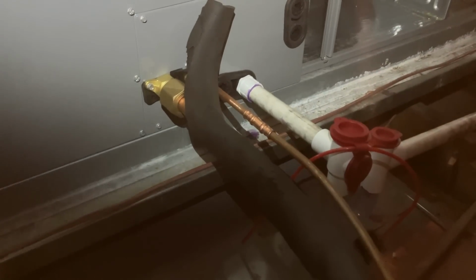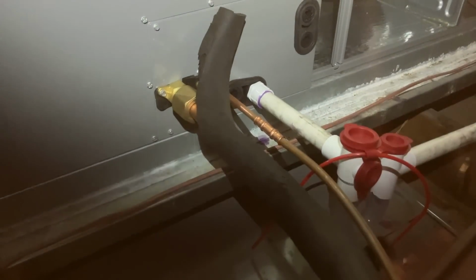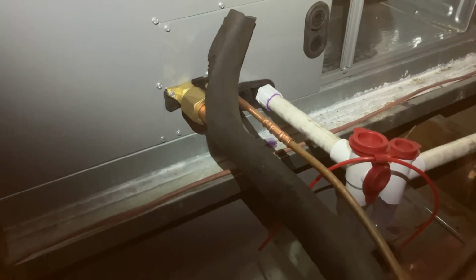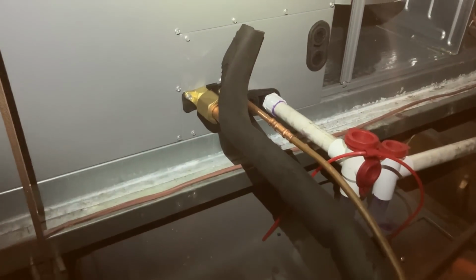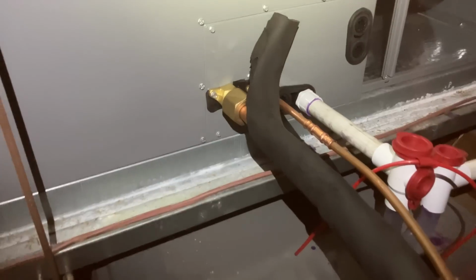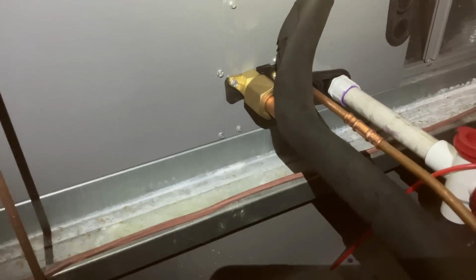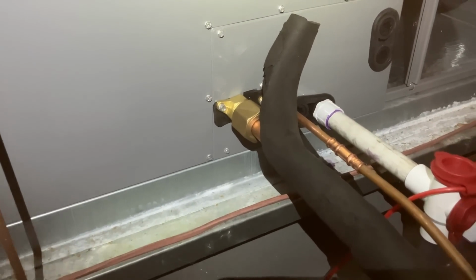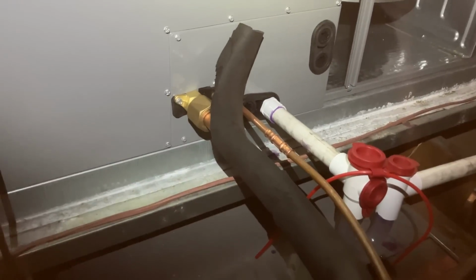Less insurance liability, and less risk of contamination getting into the refrigeration cycle circuit if you're not purging enough nitrogen, or you don't purge nitrogen at all. But this really came out nice. We're going to cut back this Armaflex insulation on the 7/8 piping. We're going to wrap the nuts with the insulation that's factory supplied. We'll put the cover on, and God willing, we'll be able to fire this up in a moment.